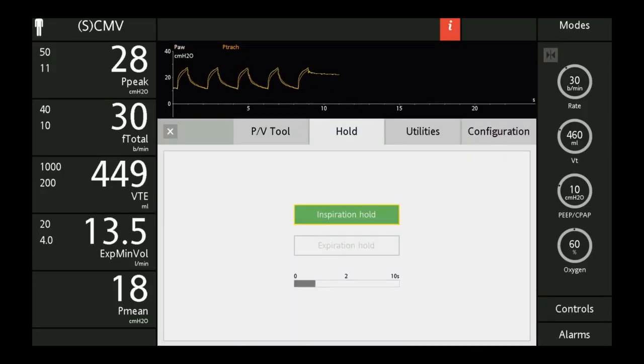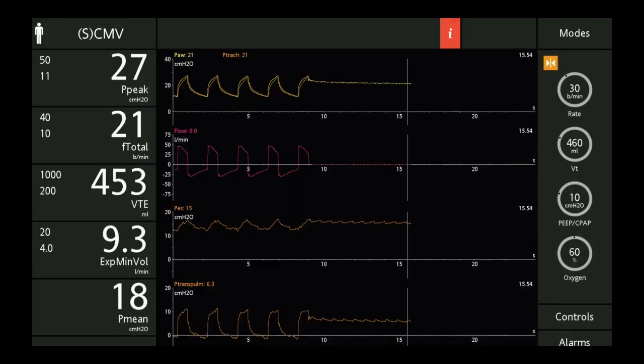After that, you're going to be performing an inspiratory hold. Now for this, we are looking for anything less than 25. If it is above 25, this will indicate that your tidal volume is too high and will need to be decreased.